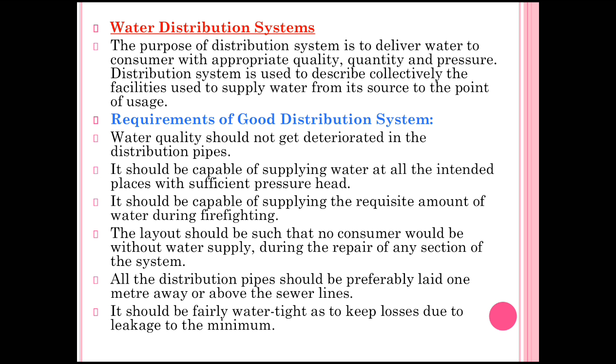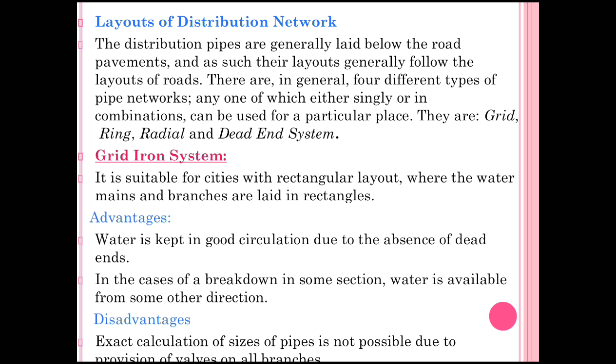All distribution pipes should preferably be laid one meter away or above the sewer lines. The system should be fairly watertight to keep losses due to leakage to the minimum. Regarding the layout of the distribution network: distribution pipes are generally laid below the road pavement, and their layouts generally follow the layouts of roads. There are in general four different types of pipe networks, any one of which — either singly or in combination — can be used: grid iron, ring, radial, and dead-end systems.